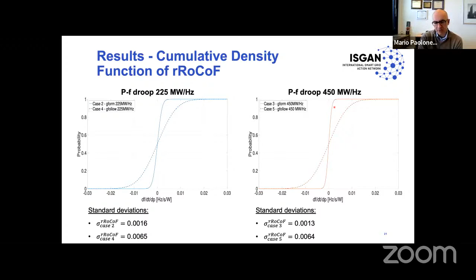In conclusion, the research experimentally validated the grid forming control of battery energy storage systems, providing multiple services using a medium voltage, utility-scale battery energy storage system hosted on the EPFL medium voltage feeder. We proposed metrics quantifying the superior performance of grid forming control compared to grid following, and we analyzed the scale-up of this conclusion to the low inertia IEEE 39 bus benchmark network, which again demonstrated grid forming superiority in terms of improving system frequency containment.